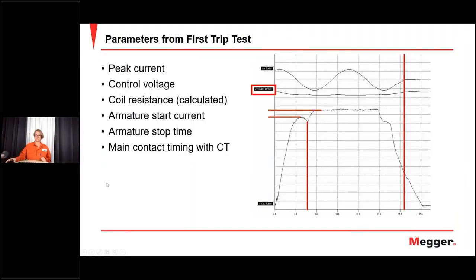Here we have an example. We look at the peak current here. We look at the control voltage here. And we calculate the resistance of the circuit. We look at armature start current, the stop time, and we look at main contact timing with the CT. We look at that. We have a sinus and it gets interrupted here at around 30 milliseconds. So we get an indication of the trip time, get an opening time.